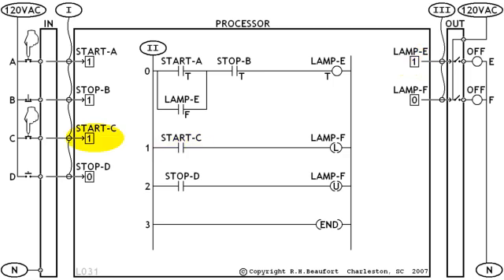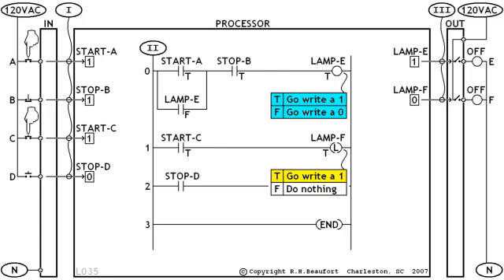This says go look for a one. Do we have a one? Yes. So this is true. And this has true coming in. And the rule says if true comes in, go write a one. Let's make a quick comparison between the rules for the OTL latch instruction and those for an OTE. Notice that they both go write a one when true comes in, but the latch does nothing when the processor executes it with false logic. Now back to the scan.